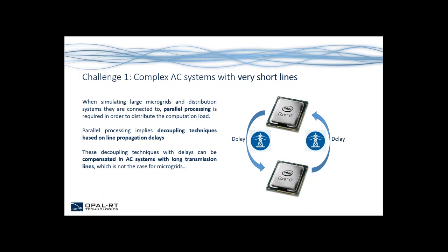The first challenge related to power systems is the fact that there are complex AC systems with very short lines that need to be simulated in real-time. When simulating large microgrids and the distribution systems they are connected to, parallel processing is required to distribute the computation load. Parallel processing necessarily implies using various decoupling techniques based on line propagation delays, and these delays can be compensated in AC systems with long transmission lines — but long transmission lines are typically not available in microgrids.